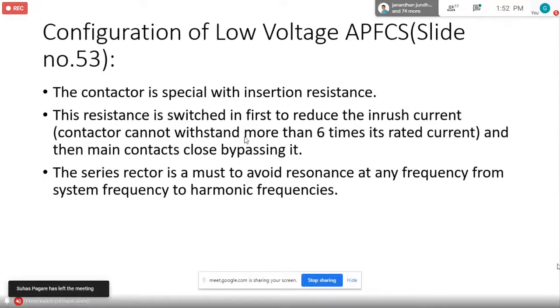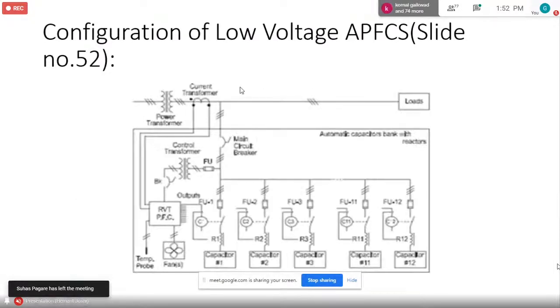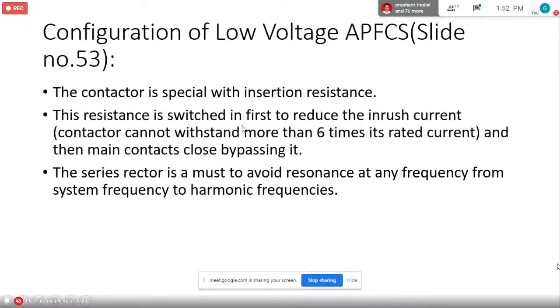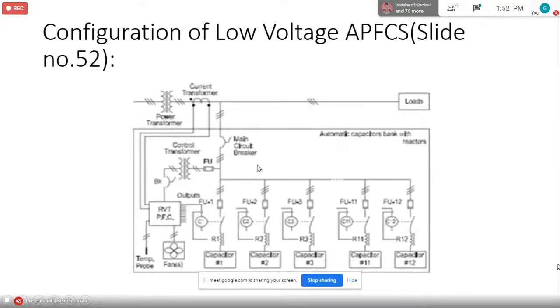So when you are checking this drawing from the vendor, from the supplier, make sure this contactor is the capacitor duty type. That means it has insertion resistance. Some manufacturers are stupid. They will provide you an ordinary contactor, which is used for switching light circuits or motors. It is not good enough. It will burn. Mostly they will supply the contactor which is used for switching on the lights.